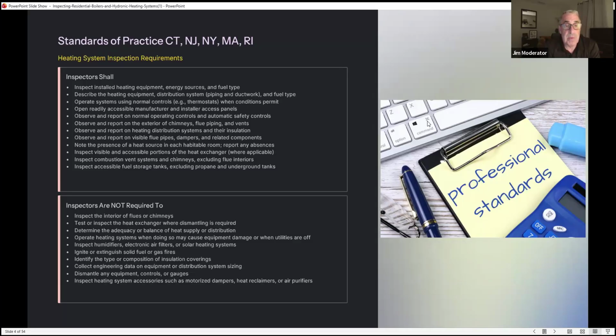Inspect visible and accessible portions of the heat exchanger where applicable. Inspect combustion vent systems and chimneys, including flue interiors. Inspect accessible fuel storage tanks, excluding propane and underground tanks. Inspectors are not required to inspect the interior of flues or chimneys. Test or inspect the heat exchanger where dismantling is required. Determine the adequacy or balance of heating supply or distribution. Operate heating systems when doing so may cause equipment damage or when utilities are off. Inspect humidifiers, electronic air filters, or solar heating systems. Ignite or extinguish solid fuel or gas fires. Identify the type or composition of insulation coverings. Collect engineering data on equipment or distribution system sizing. Dismantle any equipment controls or gauges. Inspect heating system accessories such as motorized dampers, heat reclaimers, or air purifiers.